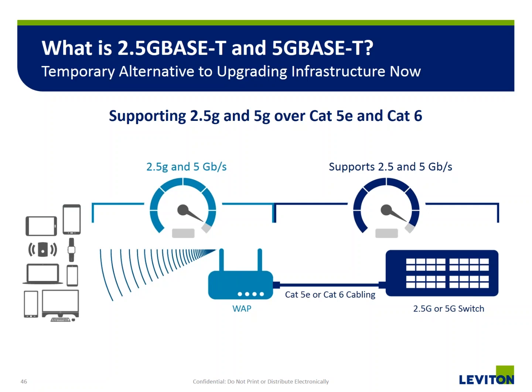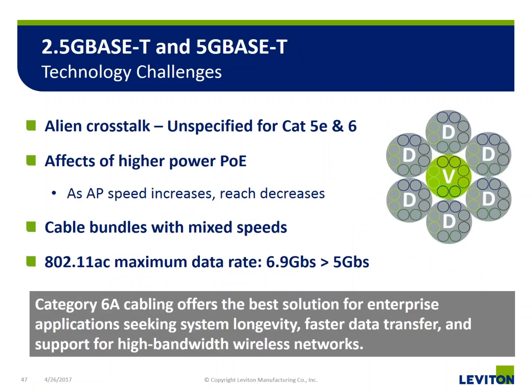Now there are some concerns to be aware of. One of the biggest challenges with 2.5 or 5G is that they operate at higher frequencies. Category 6 was designed for 250 megahertz, Category 5E for 100 megahertz, and neither was really designed to mitigate alien crosstalk the way Category 6A was.